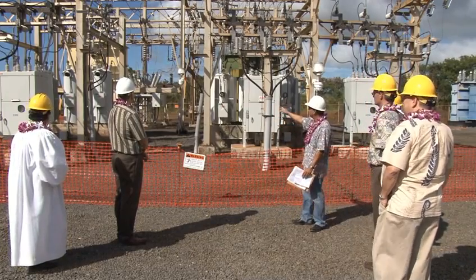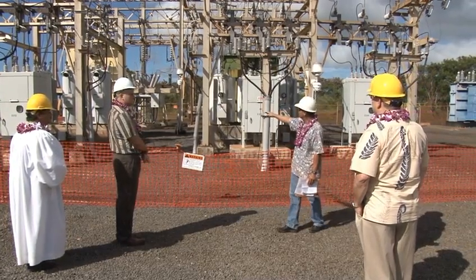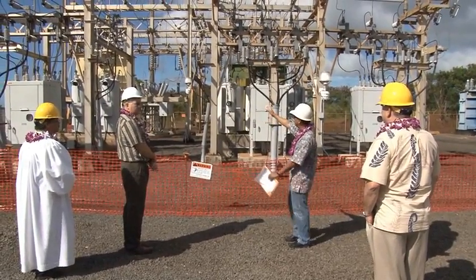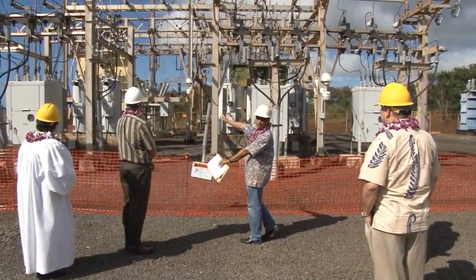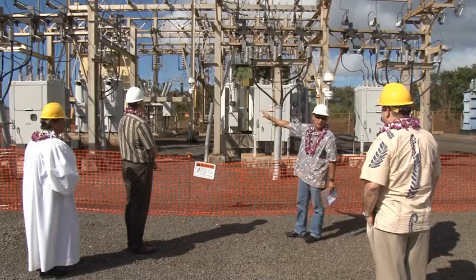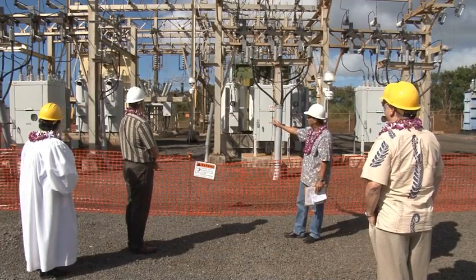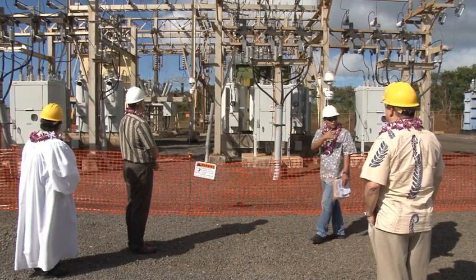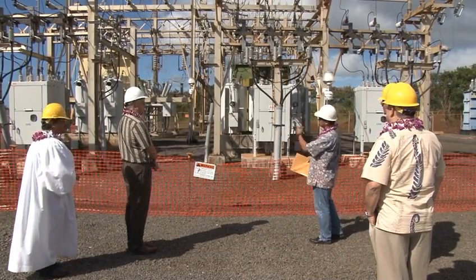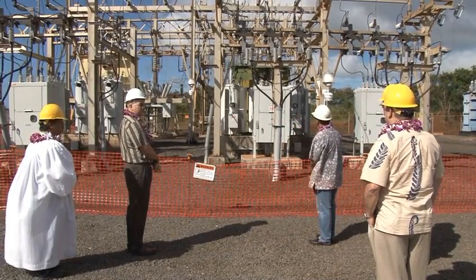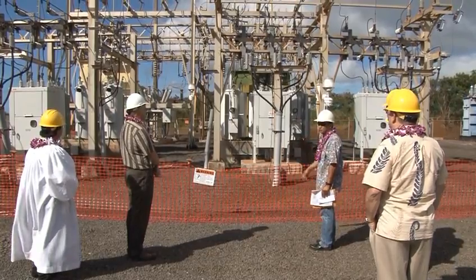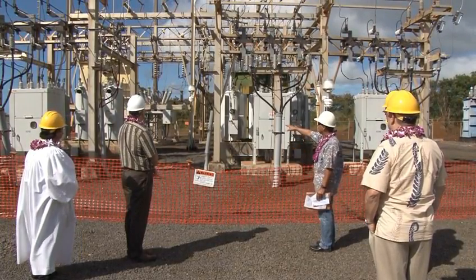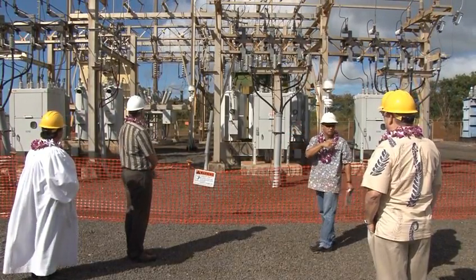The reason we have a redundancy is in case we do maintenance on one of the transformers, which means we have to take down this whole section. We wanted to make sure the PV and/or battery can still maintain the grid. So what they do in that switch is they can pretty much switch which side they want to power the grid. So just added reliability. We don't want our transformer maintenance down here to take out the use of the PV and the battery.